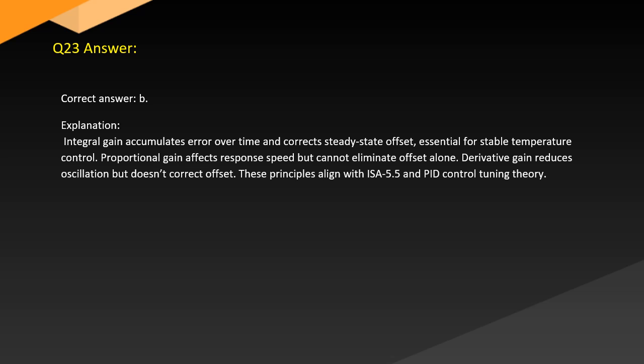Answer. Correct answer: B. Explanation. Integral gain accumulates error over time and corrects steady-state offset, essential for stable temperature control. Proportional gain affects response speed but cannot eliminate offset alone. Derivative gain reduces oscillation but doesn't correct offset. These principles align with ISA 5.5 and PID control tuning theory.